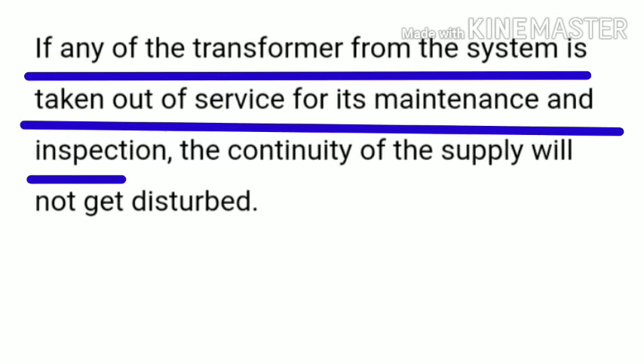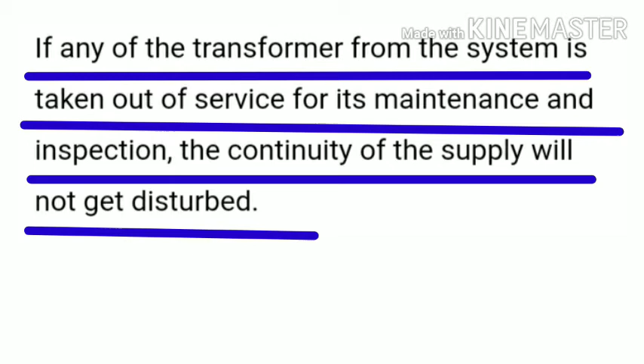So the third reason is if any transformer in the system is taken out of service for maintenance and inspection, the continuity of the supply would not be disturbed. So if we maintain some transformer, we can easily give the power supply, or continuity of the power supply. So we can have instant or continuous power supply when we make the parallel connection of a transformer. It is the reason for the parallel connection of a transformer.